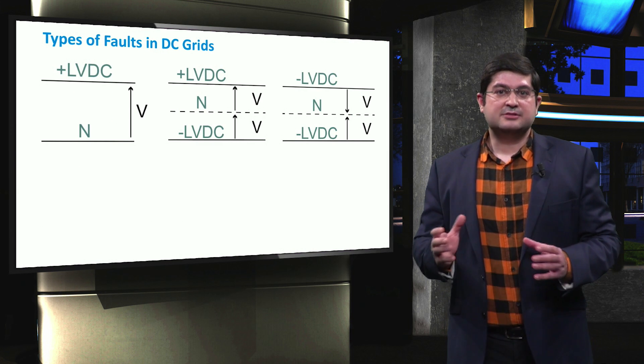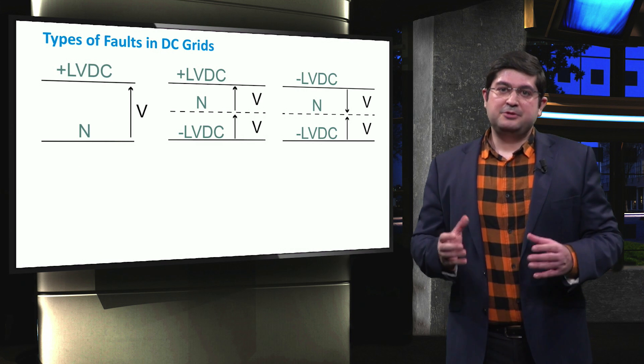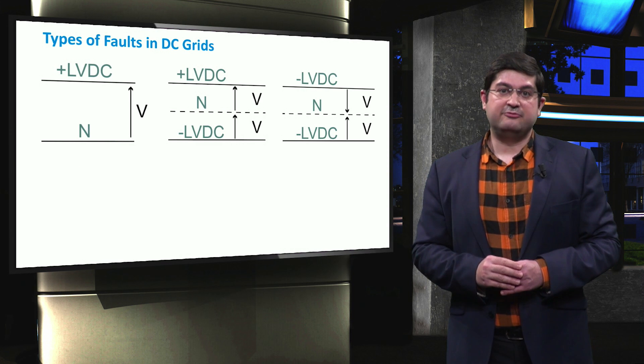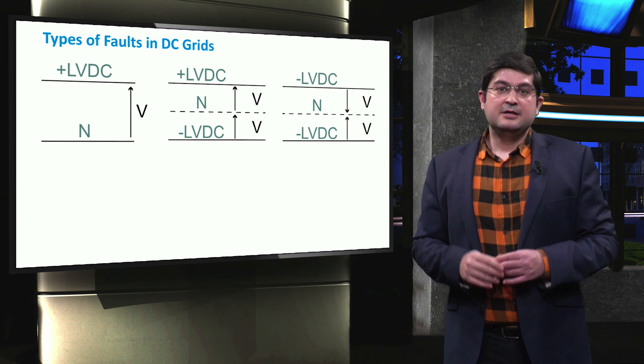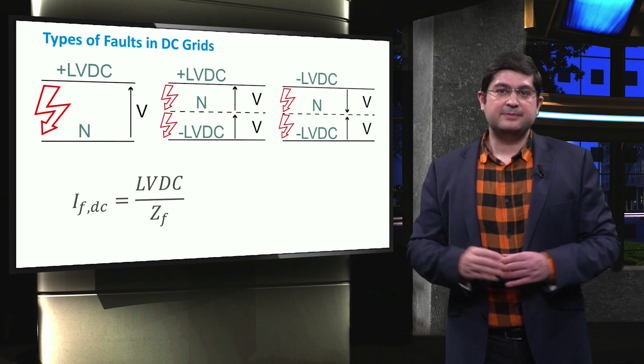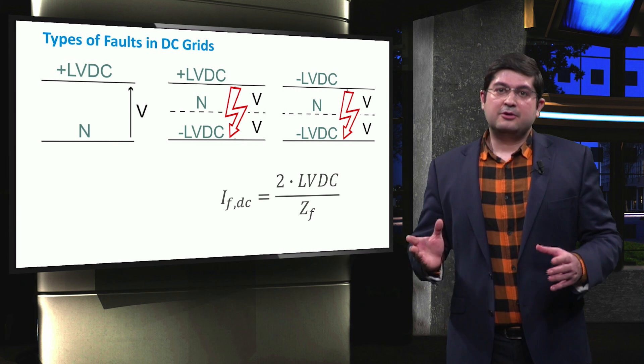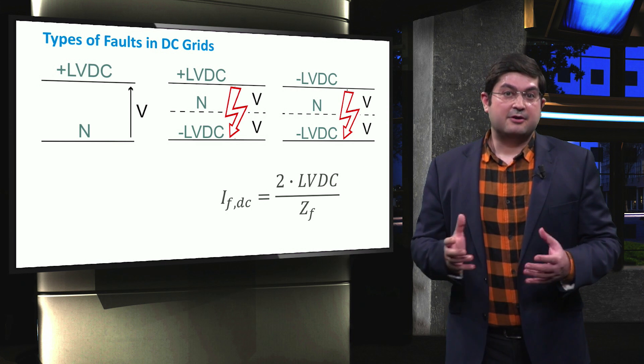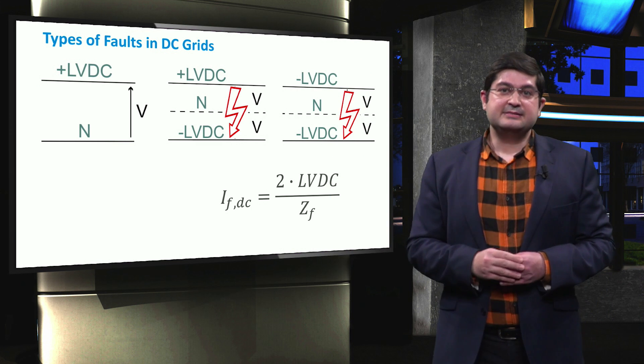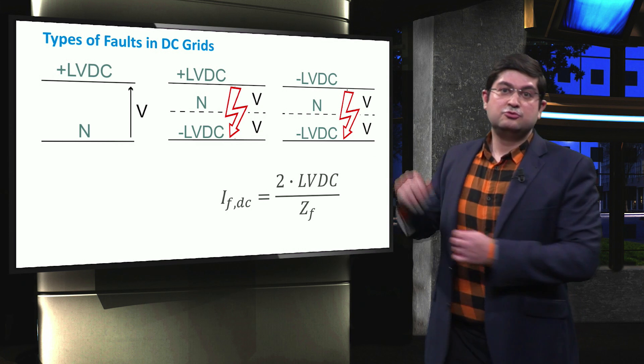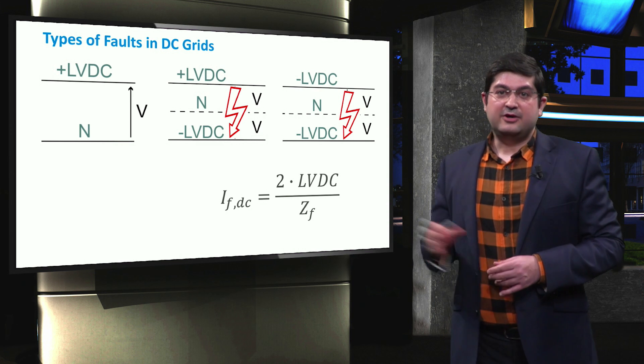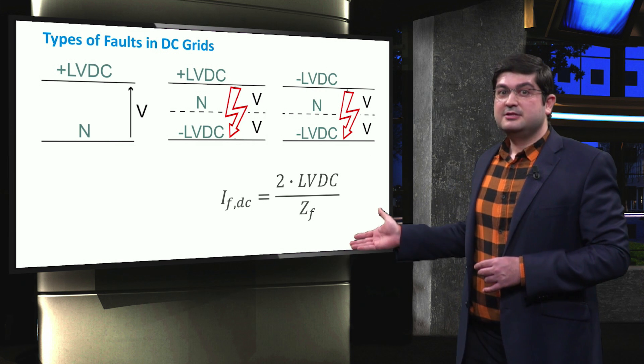Now, let's have a look into the various types of faults in a DC grid. In the previous weeks, we had introduced three DC connection types of monopolar, bipolar, and homopolar types. Two types of fault can occur in these connections. The first one is the fault from the pole to the ground. In these cases, to simplify, the line impedance is neglected and the fault DC current can be similarly calculated dividing the DC voltage LVDC by the fault impedance ZF. In the bipolar and homopolar types, the second type of fault can occur from one pole to the other pole. In this case, the voltage across the fault is equal to 2 times LVDC. Therefore, the fault current is equal to 2 times LVDC divided by fault impedance.